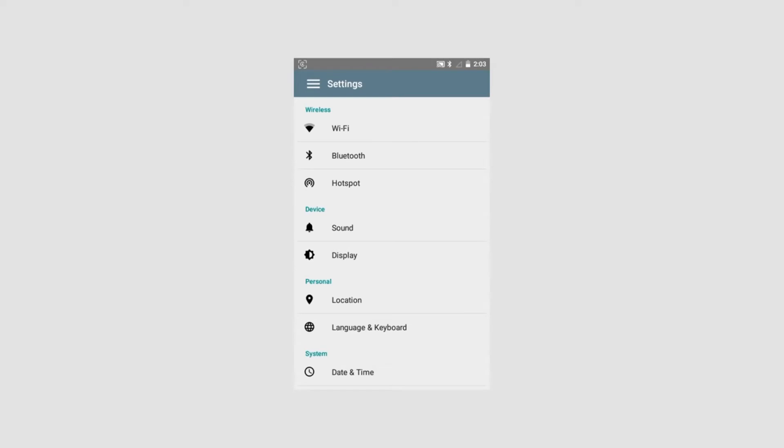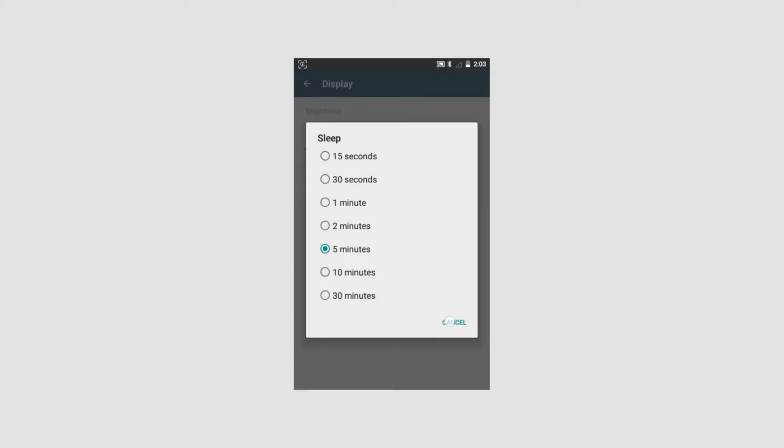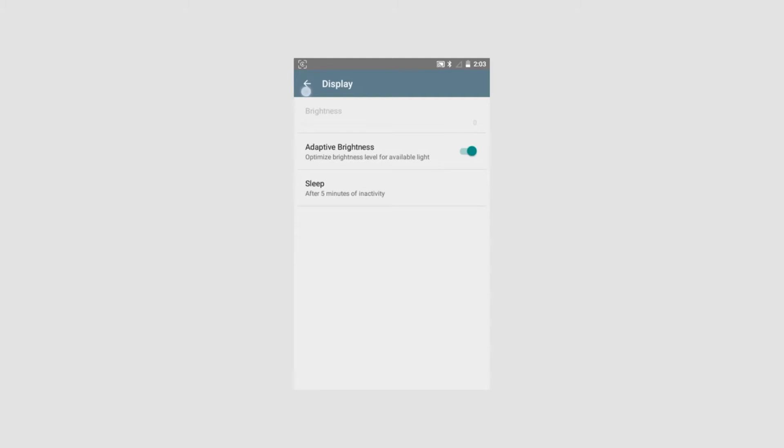Display: This section allows the user to choose between user-controlled display brightness on a scale from 0 to 100 or adaptive brightness. When the adaptive brightness is activated, the instrument adjusts the display brightness automatically according to the level of available light. The sleep function allows the user to decide after how long time the instrument automatically turns into sleep mode after inactivation. The function can be adjusted between 15 seconds and 30 minutes by tapping on the display.